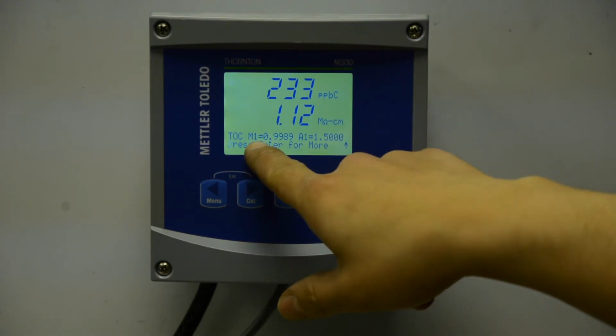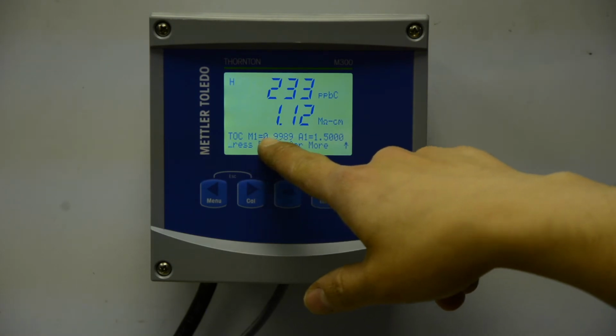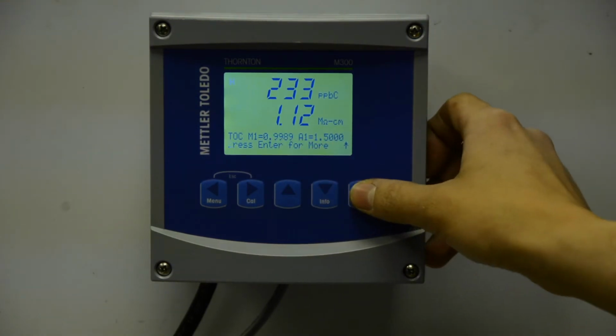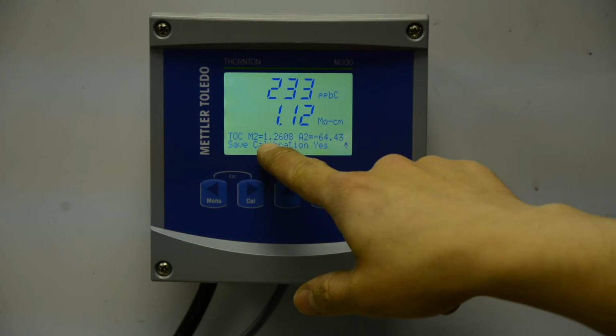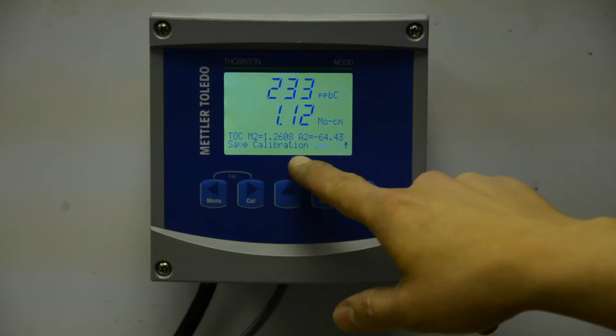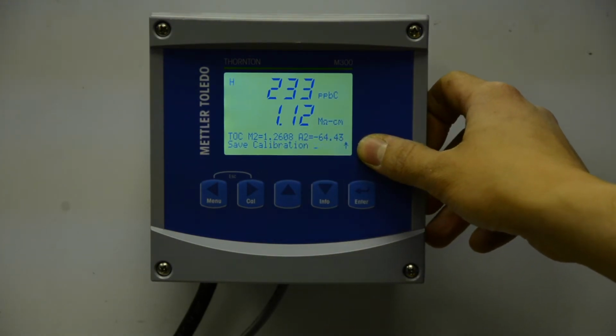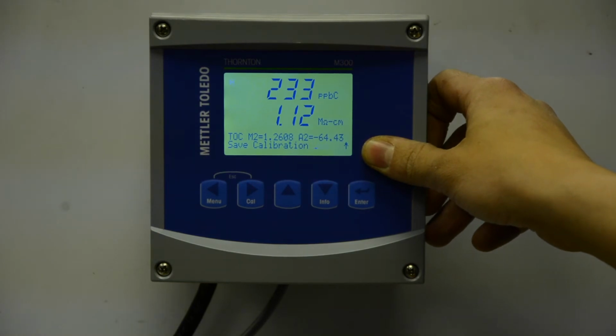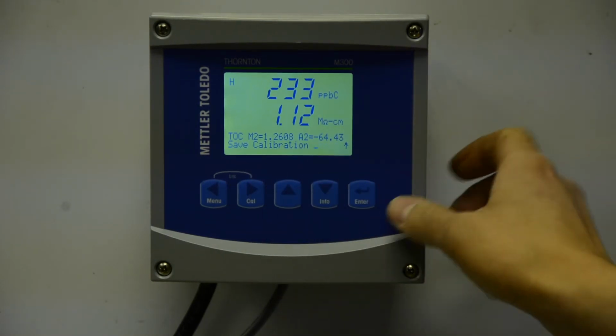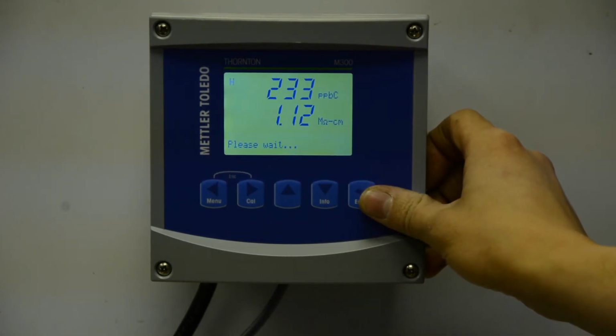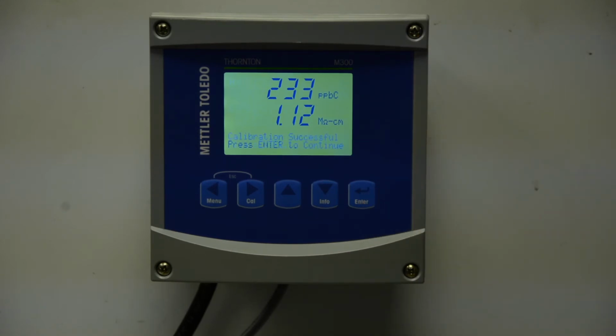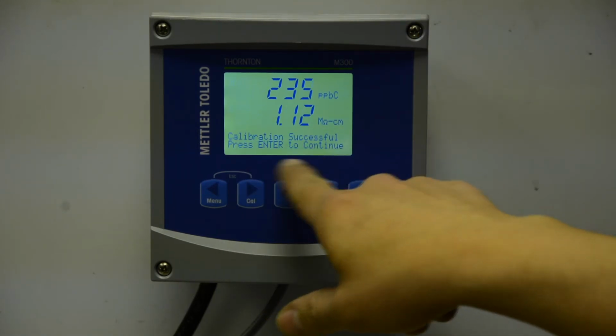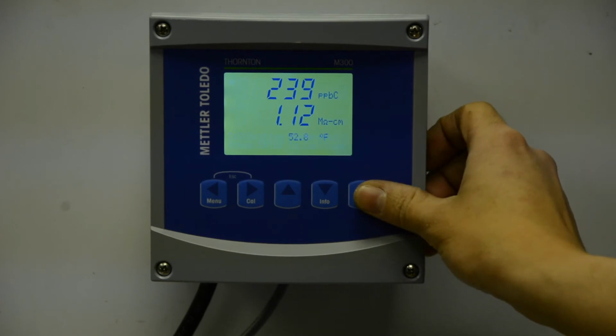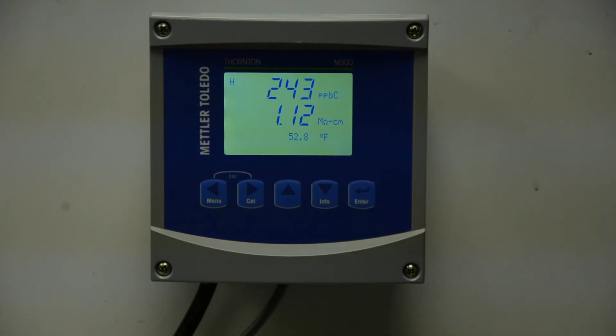Now it's showing you your multipliers and your adders. Multiplier 1, adder 1, it says press Enter for more, hit Enter. Shows you multiplier 2 and your adder 2, and asks if you want to save your calibration. Hit Yes, and that will save the calibration inside the M300 unit. If you hit No, it'll clear out all the calibration and you'll have to start all over again. So you're going to save calibration, hit Yes, and say please wait. And then your calibration is successful, press Enter to continue, hit Enter, and now your calibration is performed.